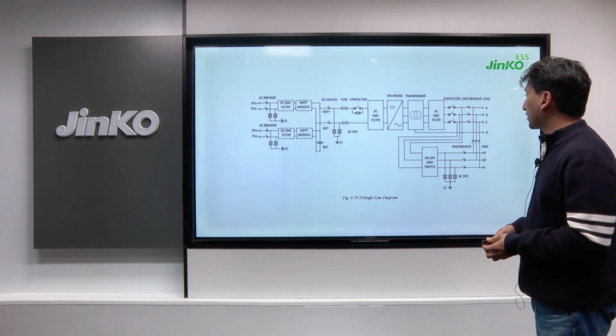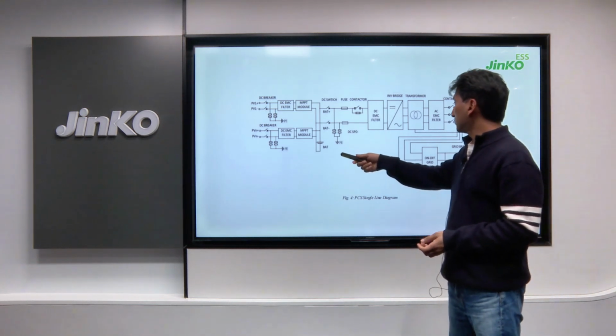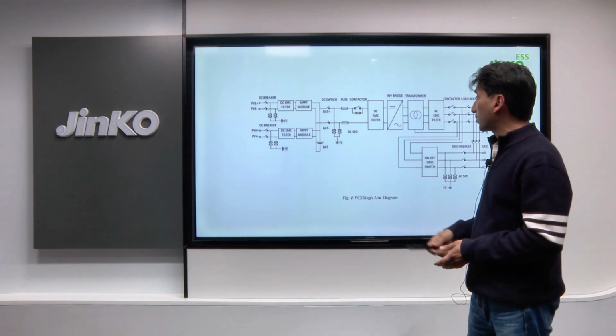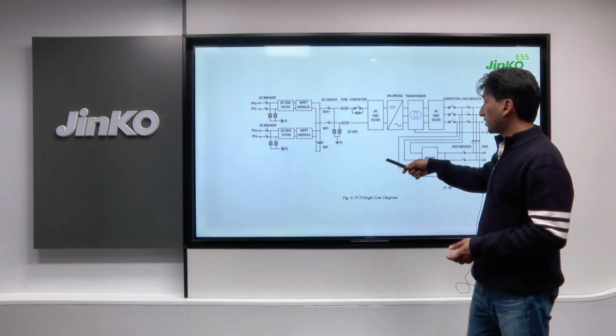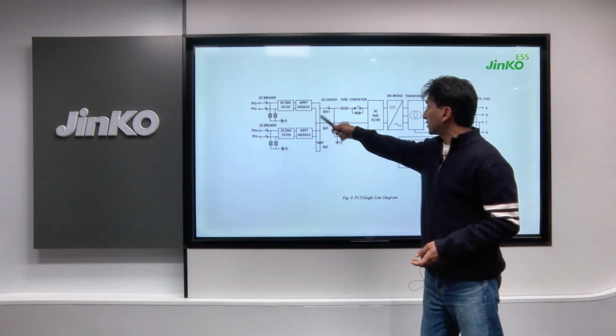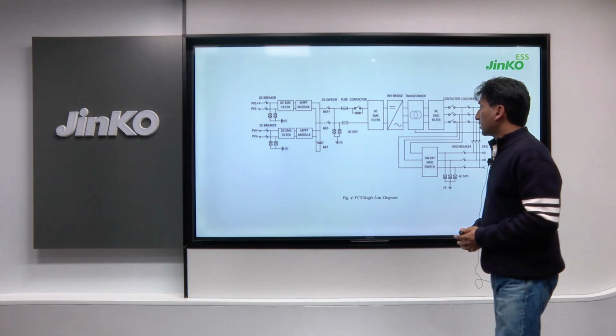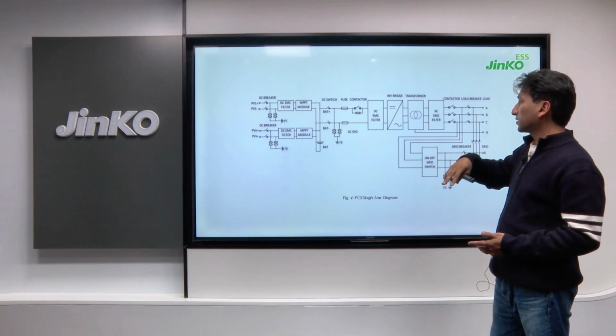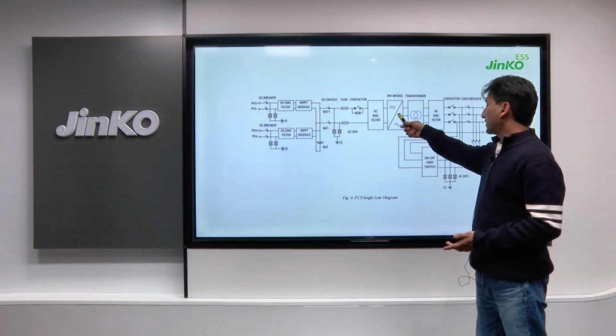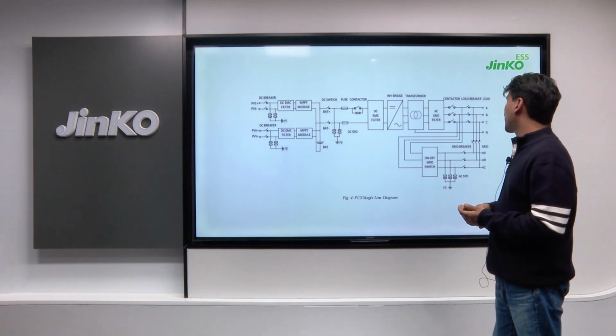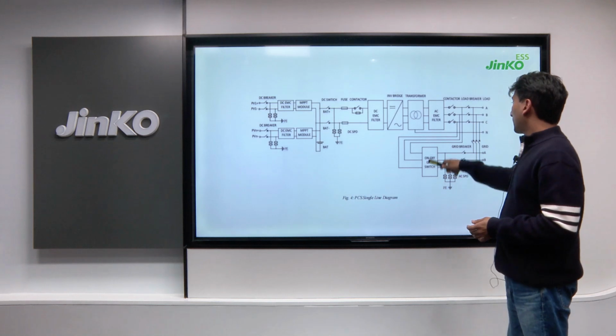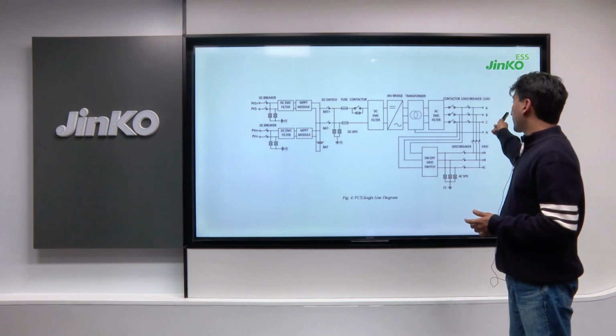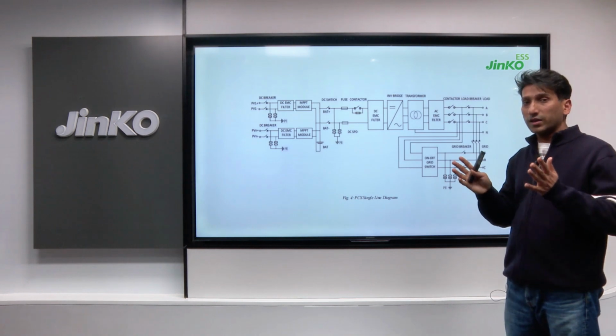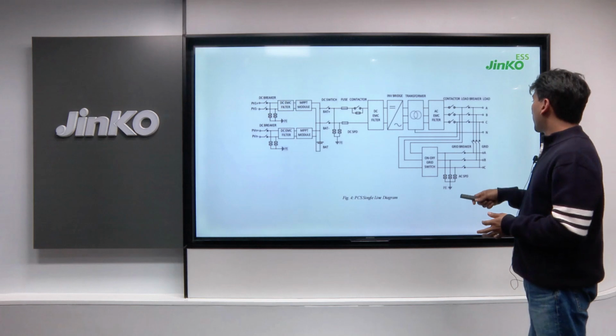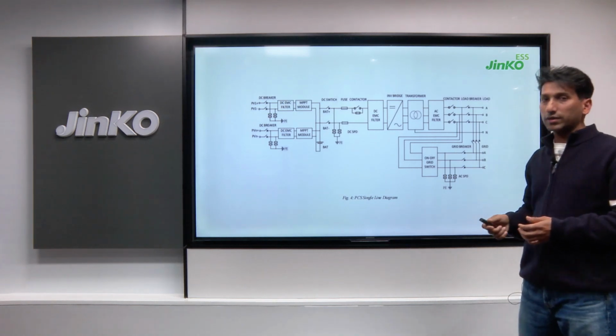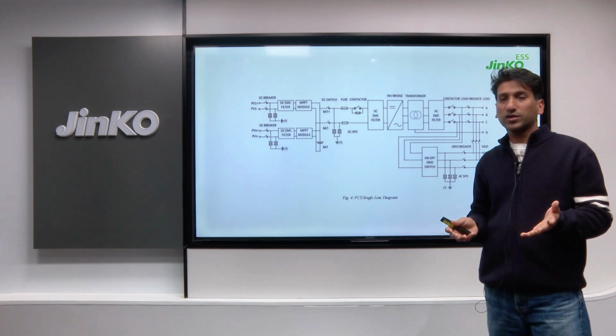Here, we have the diagram for our PCS, showing how the PCS internal structure looks. The batteries are connected on the two terminals in the PCS, which is connected to the inside inverter, the DC/AC inverter. Then we have an isolation transformer and some EMC filters, and we have two terminals on our inverter, one for the grid and the other for the load. The PCS also has many other components that we cannot discuss here.